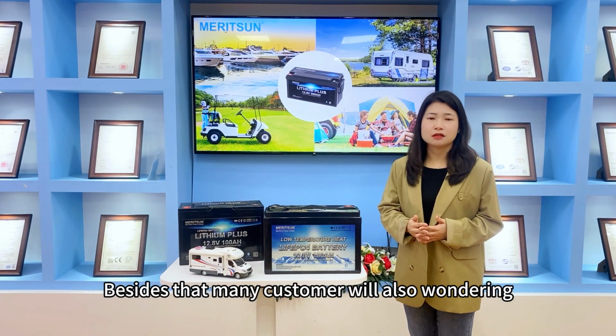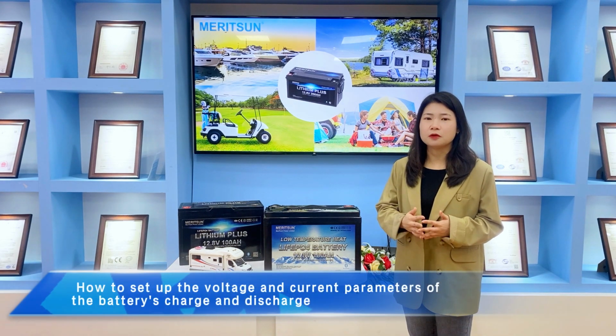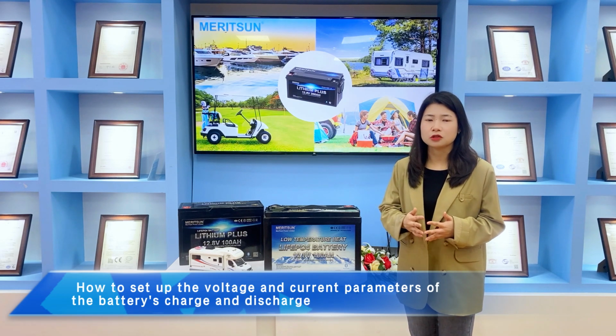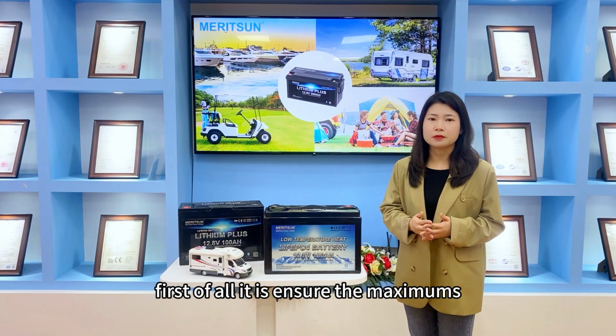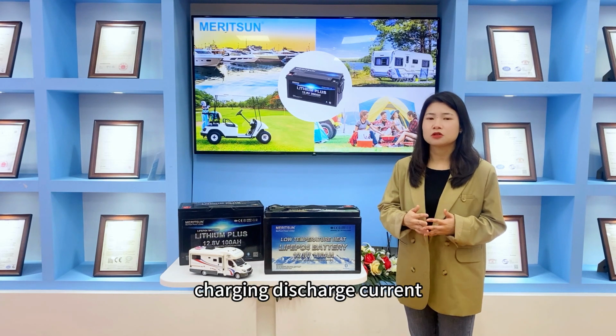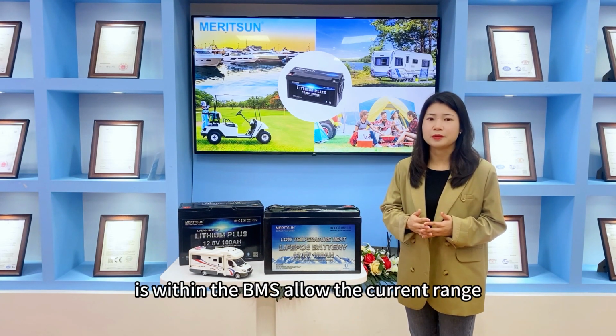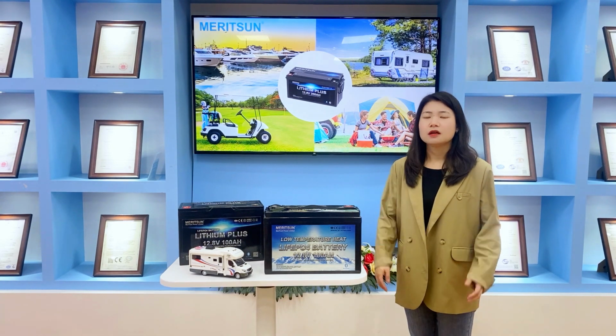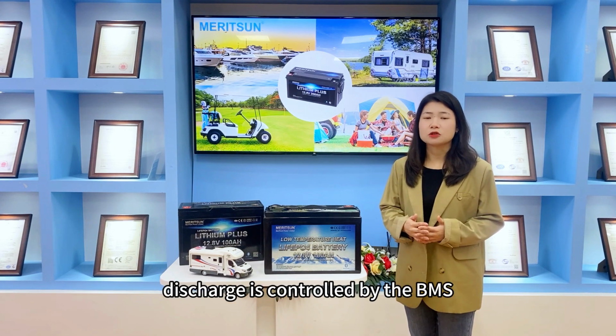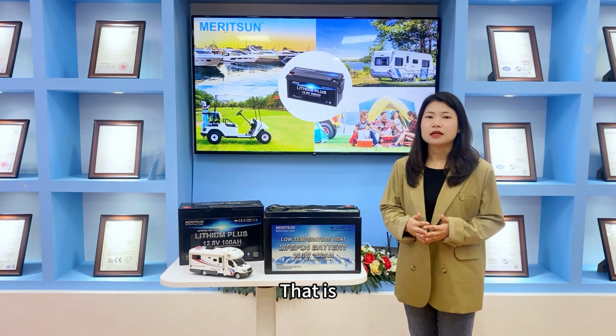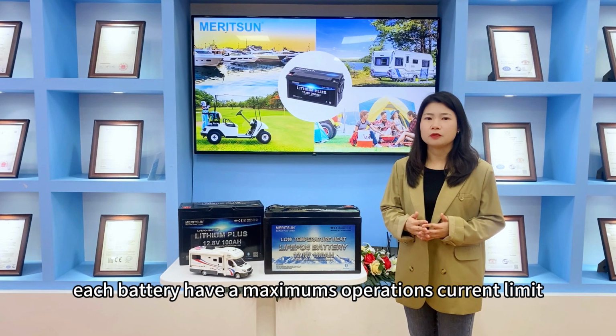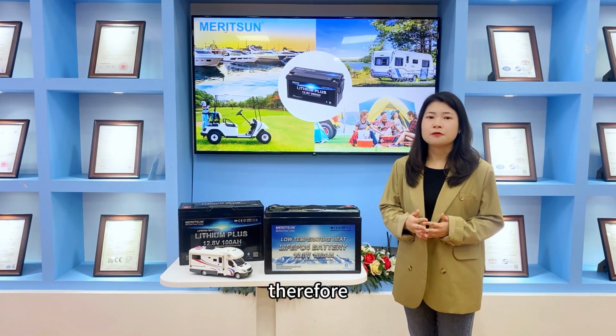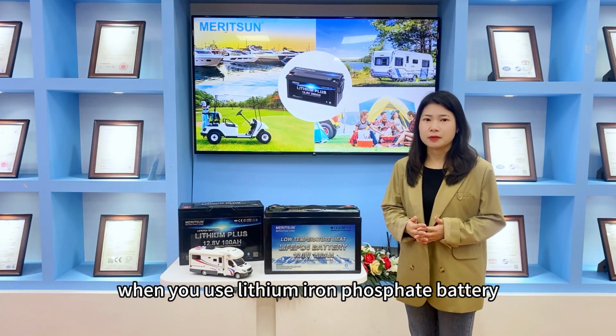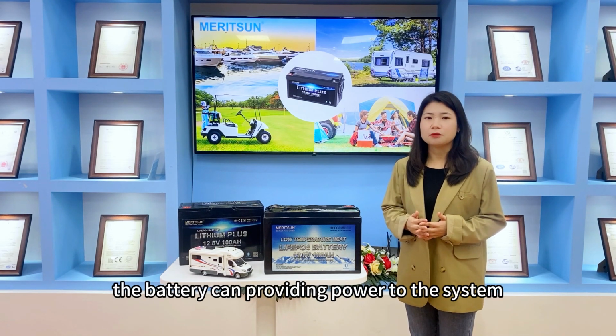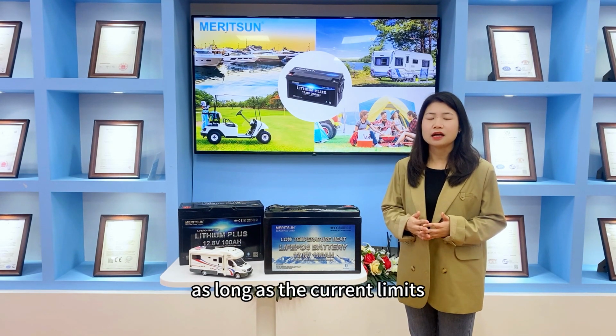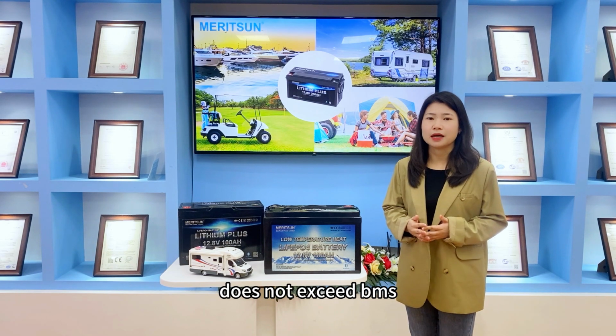Besides that, many customers were also wondering how to set up the voltage and current parameters for charge and discharge. First, ensure the maximum charge and discharge current is within the BMS current range. The battery charge and discharge is controlled by the BMS, meaning each battery has a maximum operating current limit. Therefore, when using lithium iron phosphate batteries, the battery can provide power to the system as long as the current does not exceed the BMS limit.